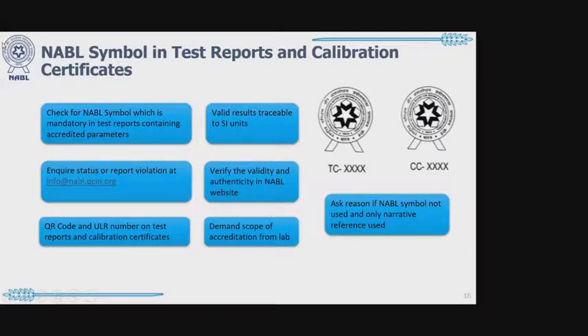This is the NABL logo, and under the NABL logo, if the TC number, a 4-digit number uniquely given to that laboratory, is mentioned, that is the proof that the laboratory is accredited by NABL, and the results within that test report are valid and traceable to SI units. Similarly for calibration, for achieving metrological traceability, the calibration laboratory also has to use the NABL symbol with the CC number. This is the accreditation certificate number given to the calibration laboratory.